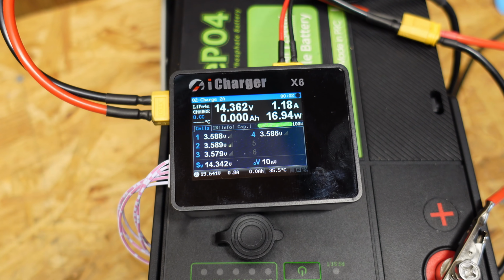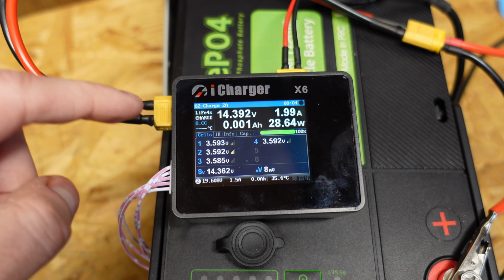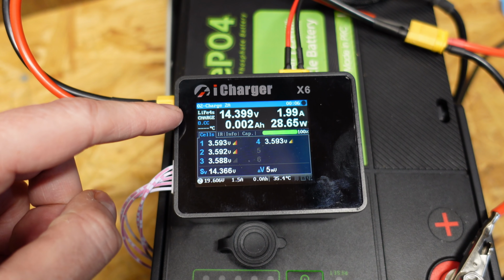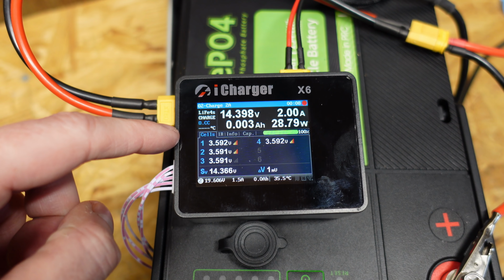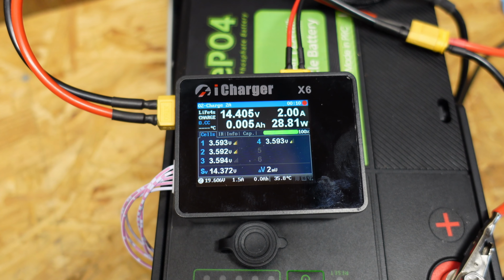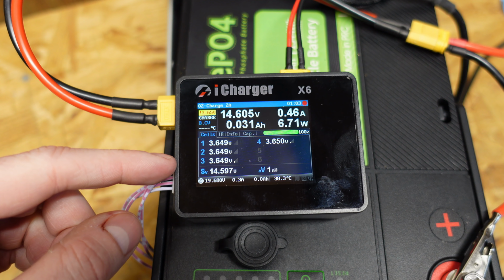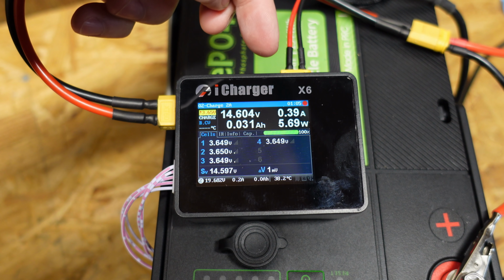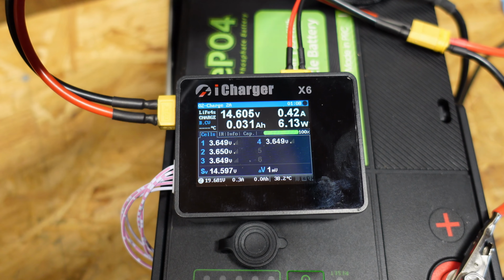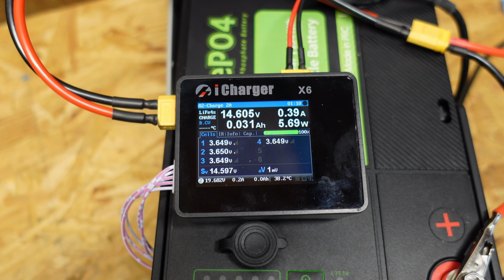So now we should be able to take this all the way up to the proper 3.65 volts per cell and let it balance out the way it's intended. So we can see now we've reached 3.65 volts on some cells, so the charging rate is throttling back to 0.4 amps as it balances this battery out.